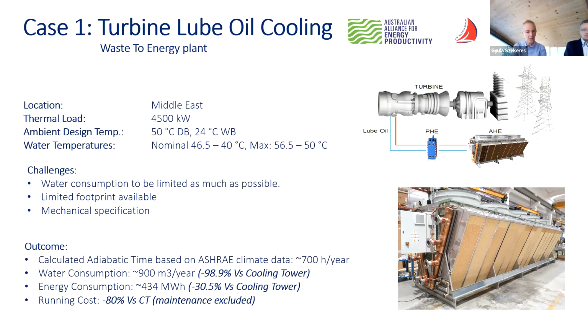We are able to precisely calculate the amount of water needed to keep the required temperature condition. This came out into a water consumption which is negligible compared to the consumption needed with a cooling tower. So we are speaking about almost 99% saving in water consumption, as well as 30% saving on energy consumption compared to an equivalent cooling tower solution, which turns into over 80% saving in operating and running cost compared to the same technology.